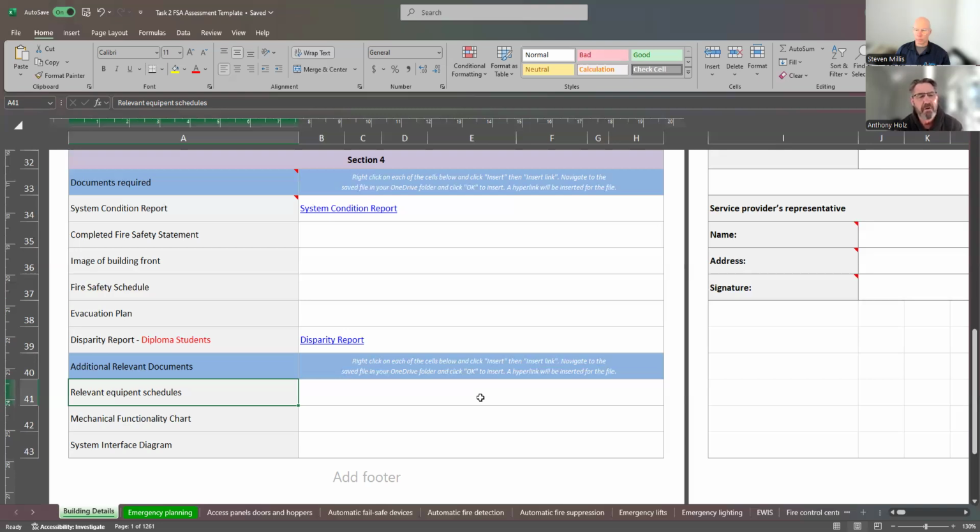because if you've got a fire door schedule, for example, and you're trying to determine whether the system's capable of performing, if you don't have a tag on a door, which is often the case, at least one door in a building, the door doesn't need to be replaced. It needs to be validated as being a fire door with a particular rating. That can be done via the schedule.